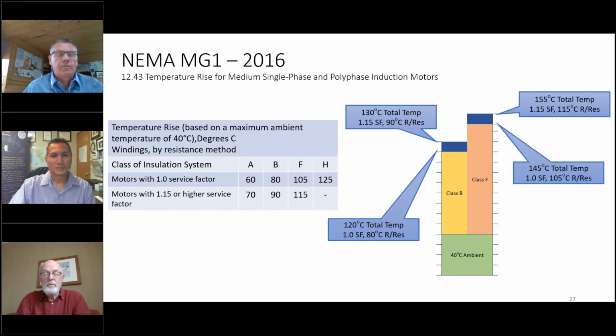So there is a cooling off period, and in large motors, they'll have safety devices or calculations called number of hot and cold starts. And that could be programmed into the multi-lin. Yeah. Automatic safety, I guess, right? Yeah. Prevent you from starting.